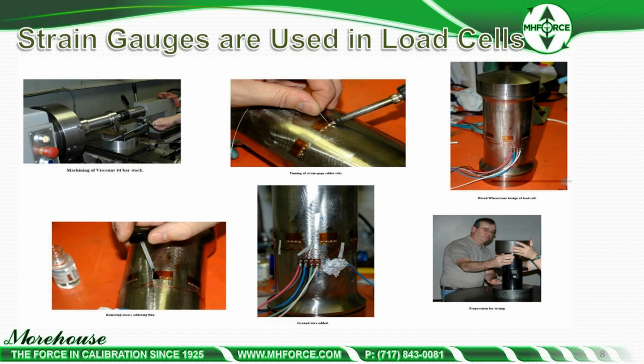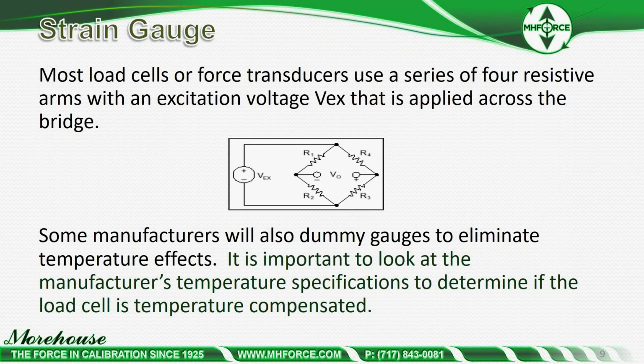We've procured a much better cell, but at the time, this was around 2004, 2005. This was a very good cell. It had a lower limit factor of about 100 pounds at 1,000,000. Now our current cell has a 13-pound lower limit factor at 1,000,000. So we made a big upgrade.